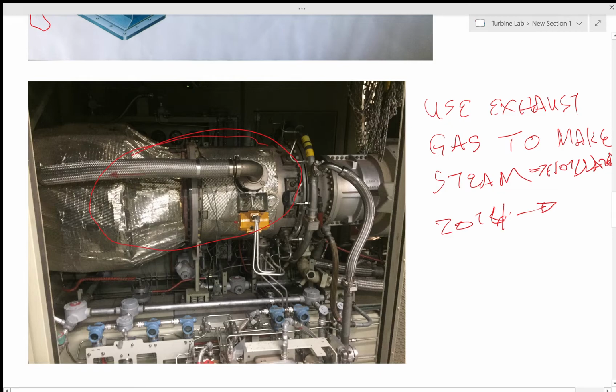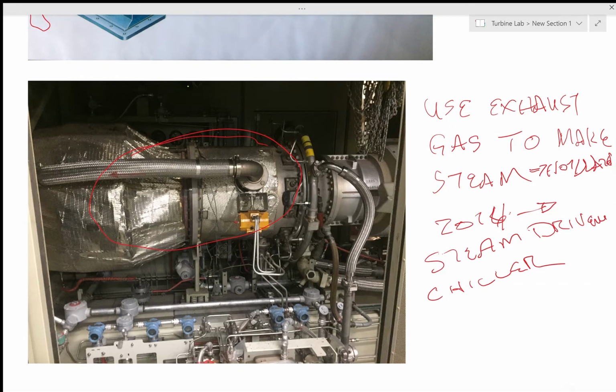So in 2014, we put in a steam-driven chiller, which makes chill water. We have a 3 million gallon tank in the parking lot on the south side of the central plant building, where we store that chill water to keep it cool. At the bottom it's about 40 to 42 degrees, and at the top it's about 55 degrees.